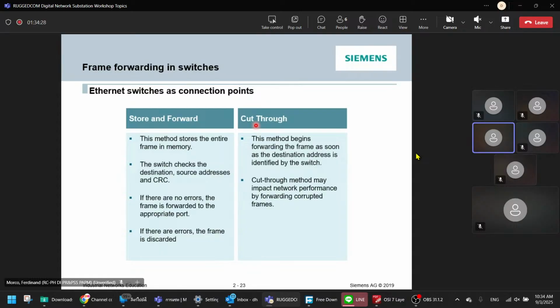Also, do we have to reconfigure it? No. You will only use cut through when you are using a PRP or HSR type of device. In the network, we use PRP, but at that level we have to select it. By default, it's PRP. And for the other switches in the LAN A, LAN B network, we don't set anything, it's always cut through, right? Okay, good.